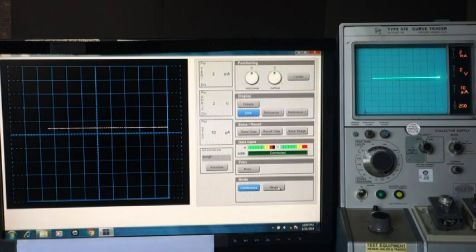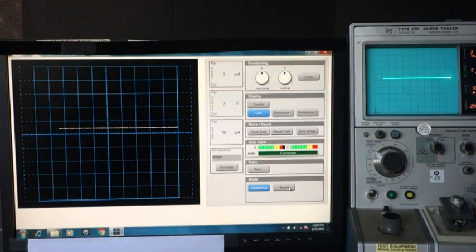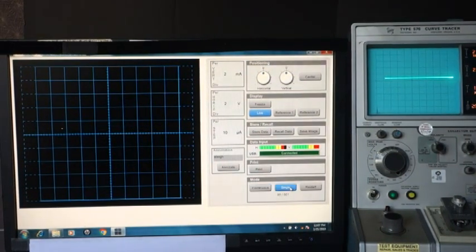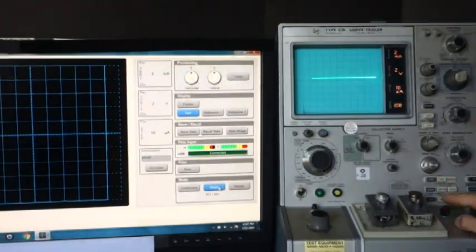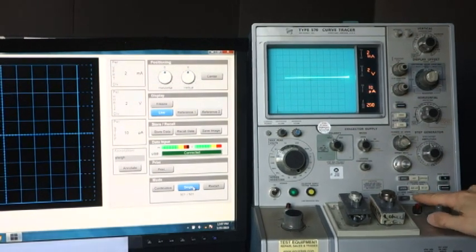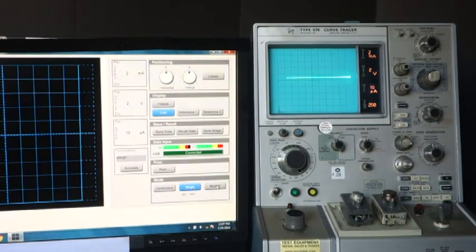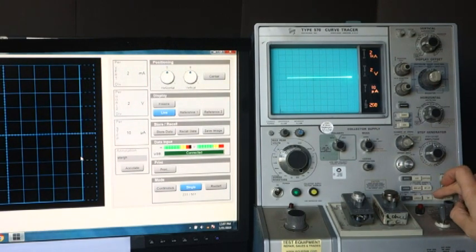In addition to normal mode, there is a DC mode on a curve tracer. So what we did, we added a mode which is called single mode. Single mode is sort of like DC mode, except you have exact control of where you take a measurement. So as you increase collector voltage manually, you can push a single button on the front panel of the curve tracer and you will store one data point in the program. You can store up to 512 data points.